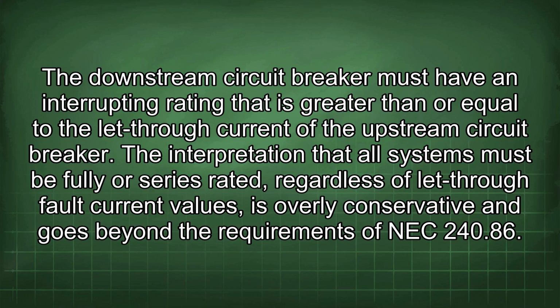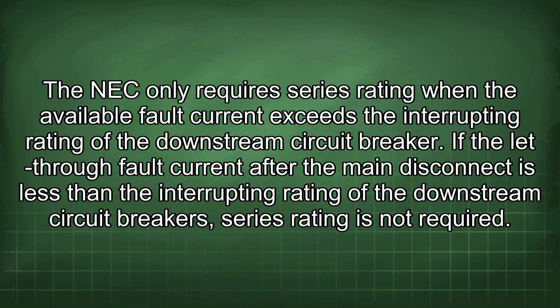The interpretation that all systems must be fully or series rated, regardless of let-through fault current values, is overly conservative and goes beyond the requirements of NEC 240.86. The NEC only requires series rating when the available fault current exceeds the interrupting rating of the downstream circuit breaker. If the let-through fault current after the main disconnect is less than the interrupting rating of the downstream circuit breakers, series rating is not required.